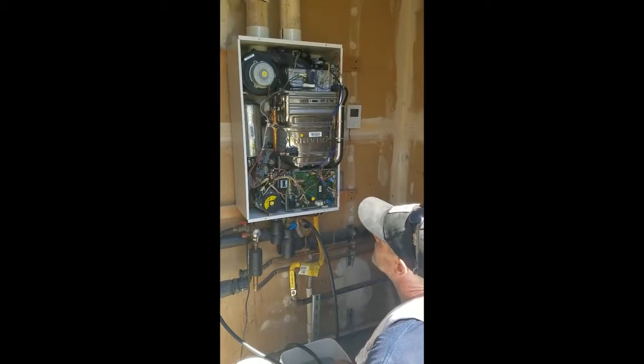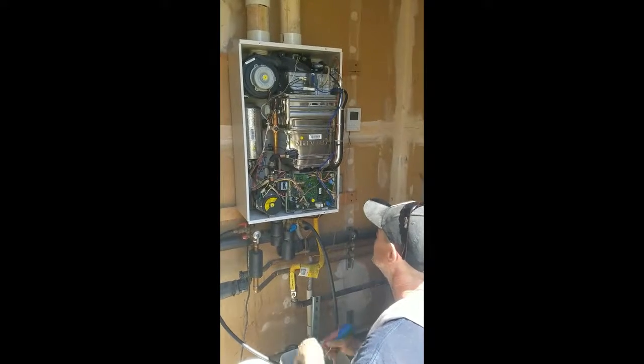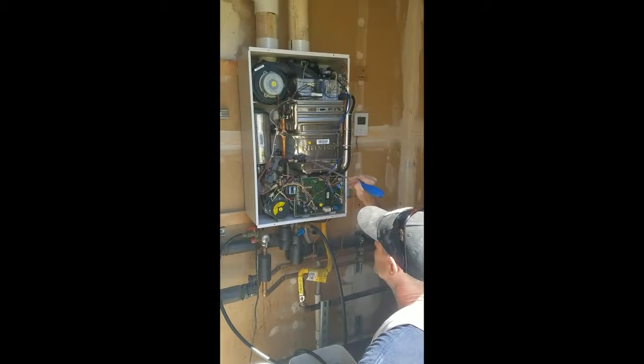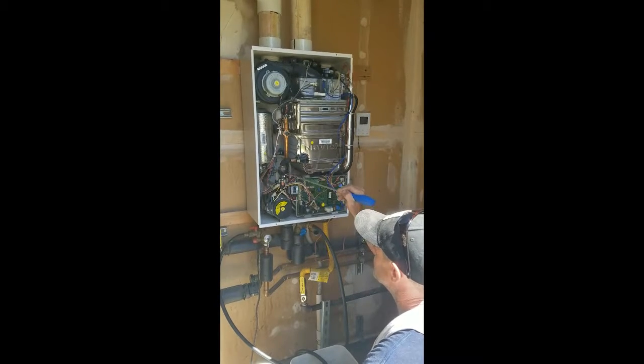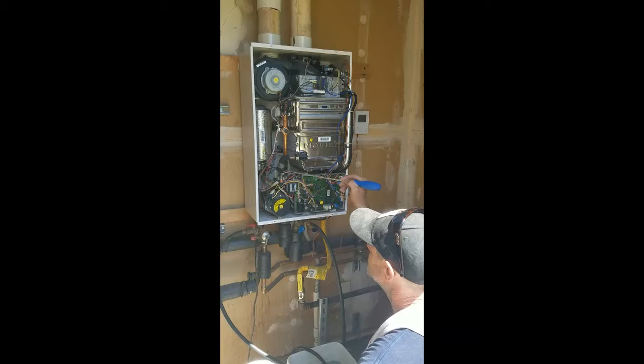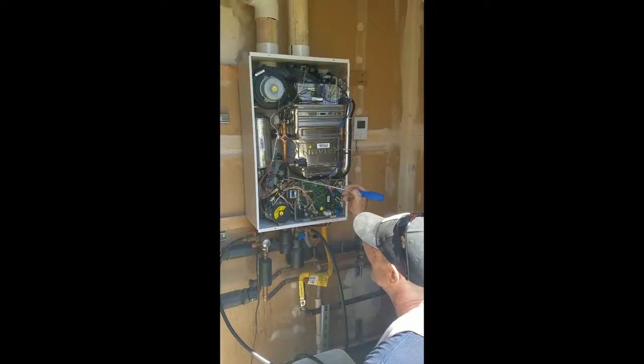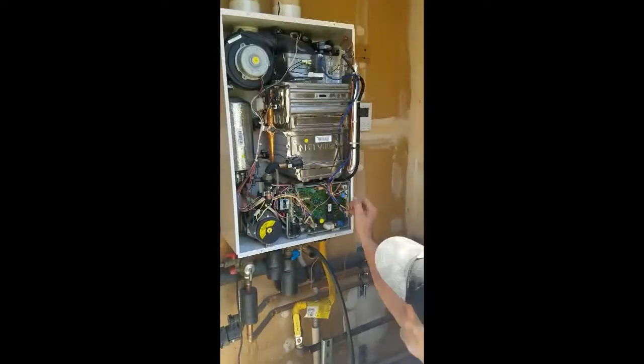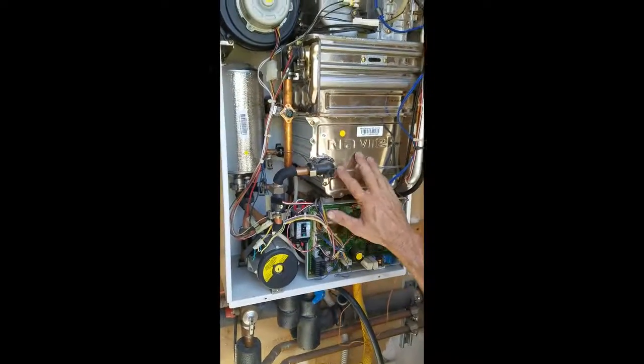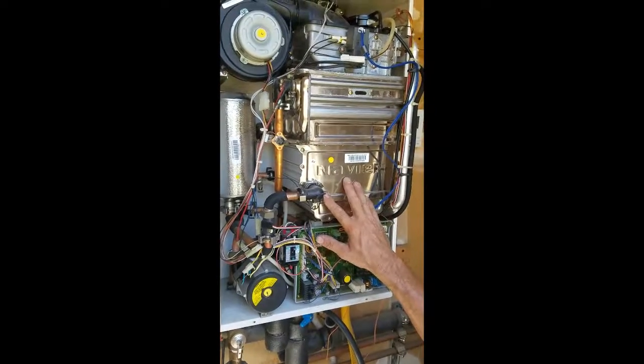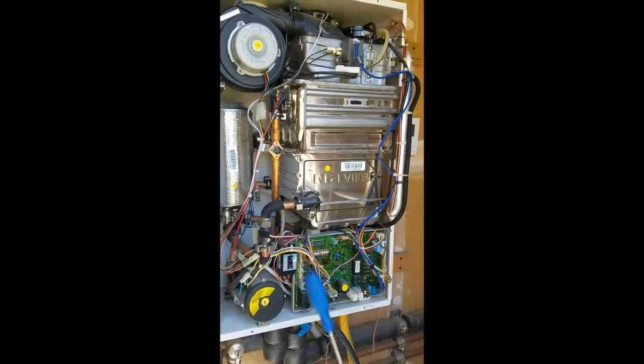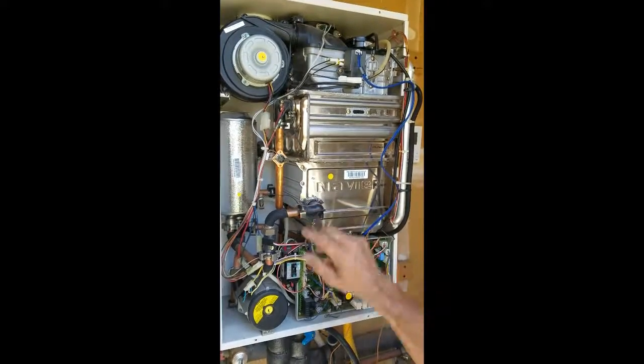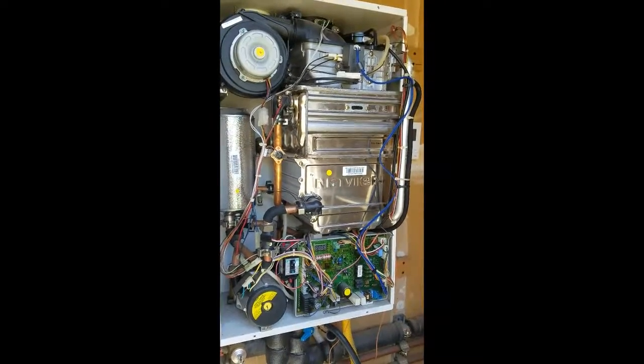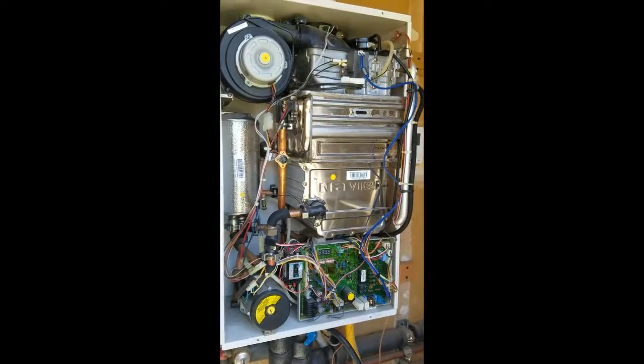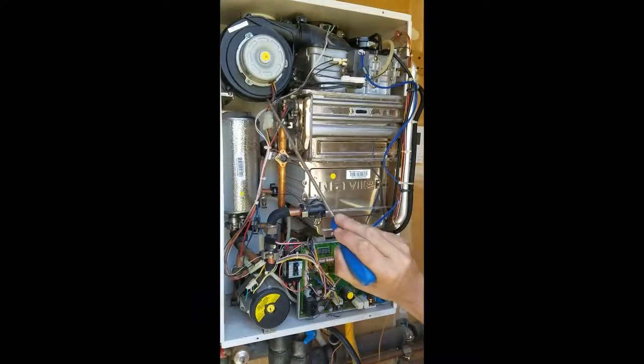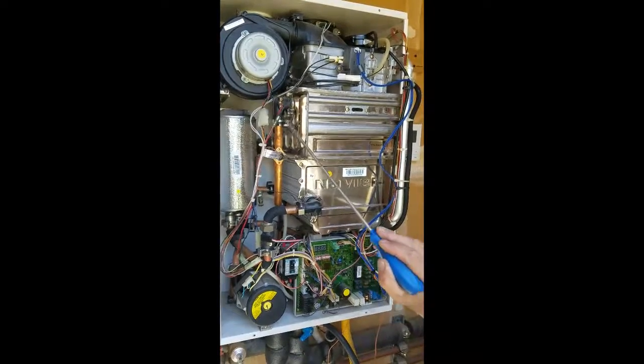Sean, what happens if they don't do the maintenance? What happens is inside these little devices, which are flow sensors, there are little props, and these are magnets. When those props get restricted from scale buildup, it doesn't send the right information to the board, and what it ultimately causes is lack of hot water. There could even be times when there's an issue you don't know about, where hot and cold water are mixing, causing your unit to run more frequently. There are quite a few flow sensors in here, and each one does a different thing.